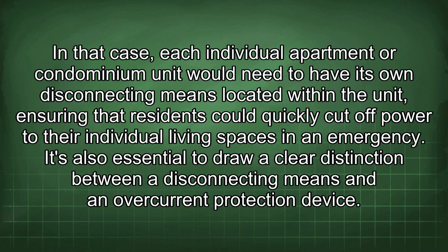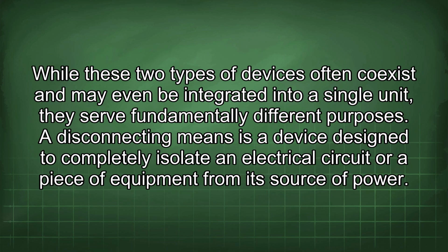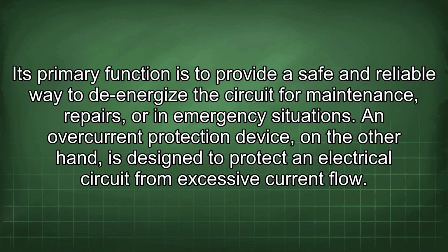It's also essential to draw a clear distinction between a disconnecting means and an overcurrent protection device. While these two types of devices often coexist and may even be integrated into a single unit, they serve fundamentally different purposes. A disconnecting means is a device designed to completely isolate an electrical circuit or a piece of equipment from its source of power.